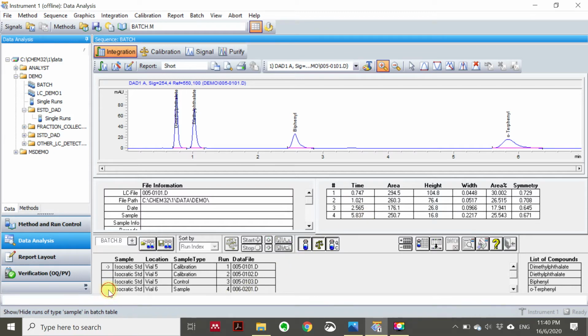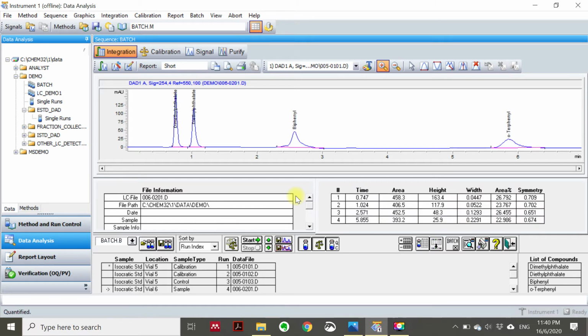When we run our sample, for example here, we open the sample. We still find four peaks in this sample solution, and the four peaks appear in this chromatogram. Based on the retention time that we capture from the calibration standard, the instrument will match the retention time in the sample. The time window is 0.05 or 0.5, it depends on our setting. Any peak within that window will be identified as the compound present in the sample.